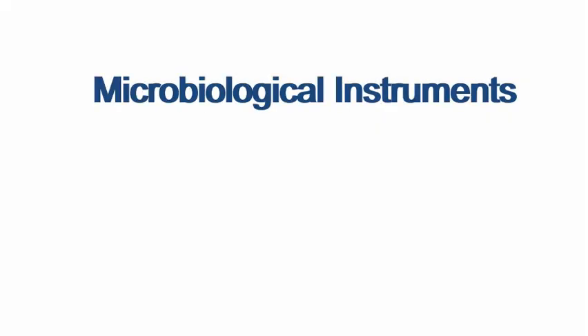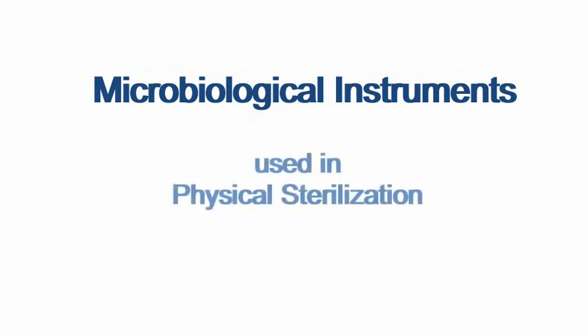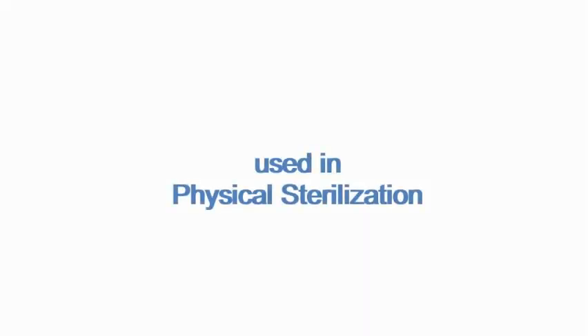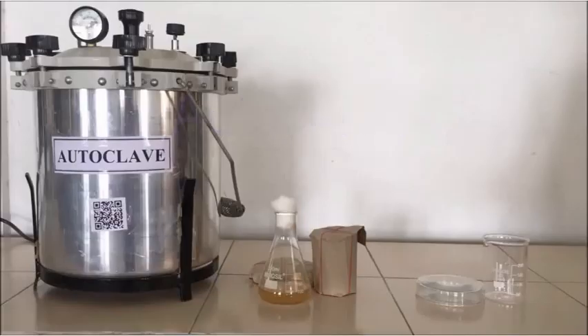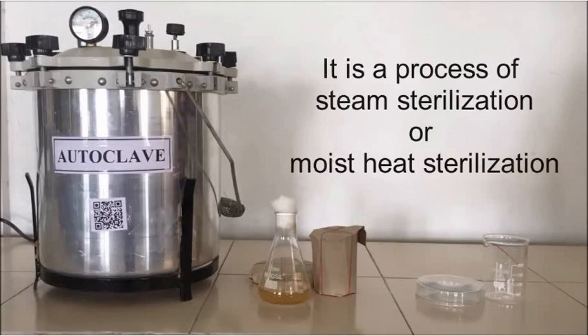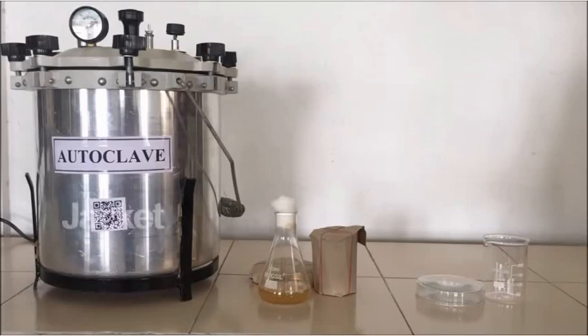This lecture is about microbiological instruments. Let's begin with instruments used in the physical sterilization process. First comes the autoclave. An autoclave is just like a pressure cooker and works on the same principle: when you increase the pressure, the boiling temperature also increases. So it works on the principle of steam or moist heat sterilization.